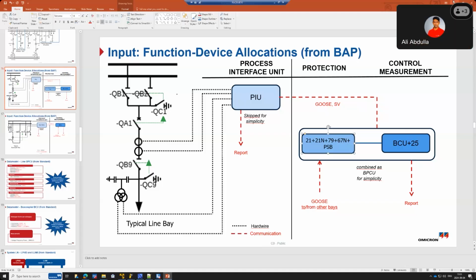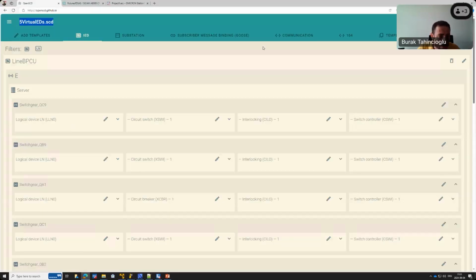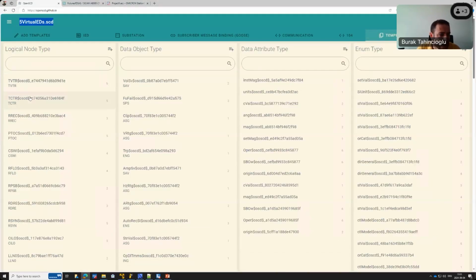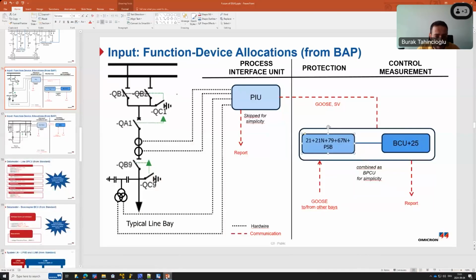And if you have IEDs that are tripping circuit breakers through a merging unit, how do you display this in the data model? How do you define it in the data model? Typically a merging unit would have the TCTR and TVTR logical nodes, as we mentioned already. This is for the data acquisition from the CTs and VTs. But if we also trip the circuit breaker, then we need to allocate the functions of XCBR and then CSWI. So we need to break up these two logical nodes into two different boxes. In that case, the PIU would have the logical node XCBR, which is the ultimate tripping. So this is the link to the trip coil.